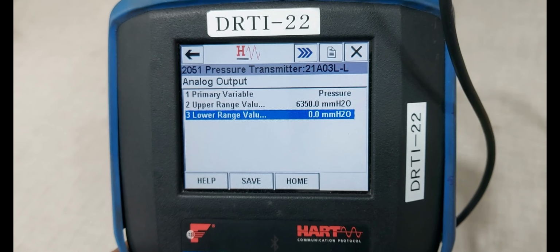Pump the pressure. It is increasing. Pressure almost reached 6,700 something. Display showing same error. Also showing the same milliamps DC. Doing the low sensor trim, we have already applied the static pressure to both sensors.